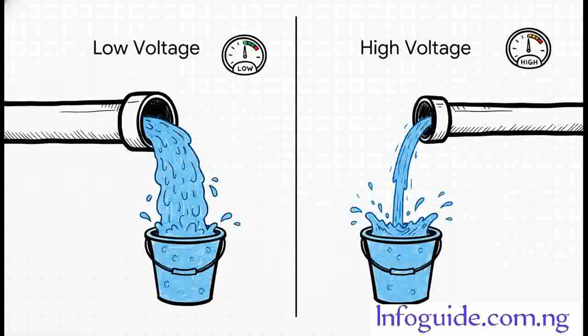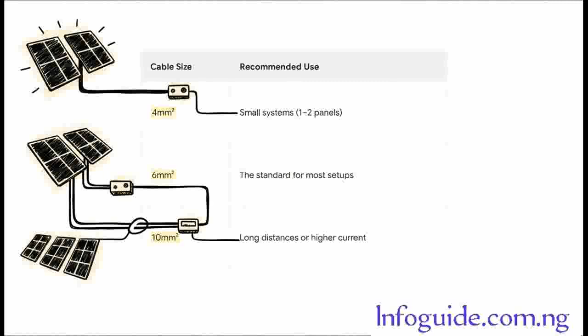For your solar panels, the sizing is pretty straightforward. A 4mm squared cable might work for 1 or 2 panels, but 6mm squared is really the go-to standard for most setups, giving you a great safety margin. You'd only need to jump up to 10mm squared for super long runs, or if you're connecting a whole bunch of panels in parallel, which really jacks up the current.